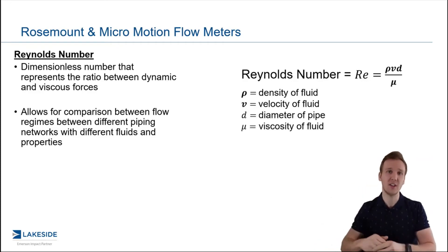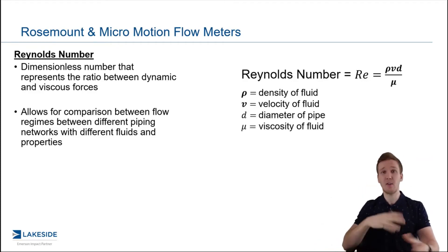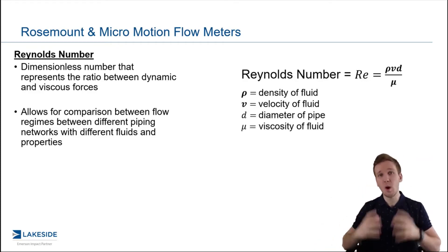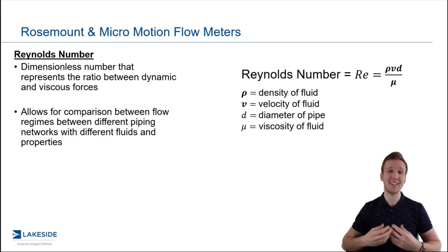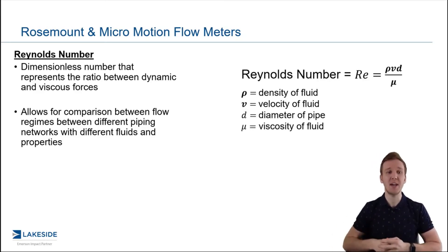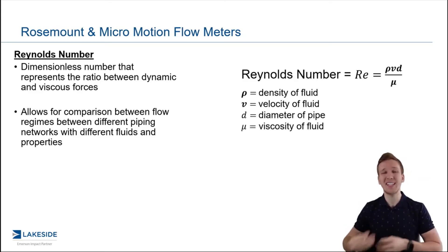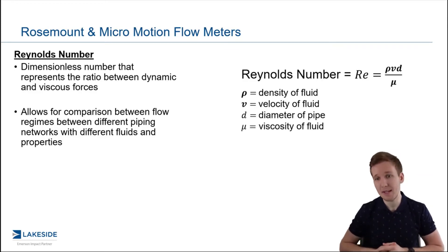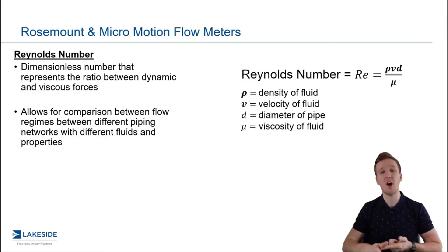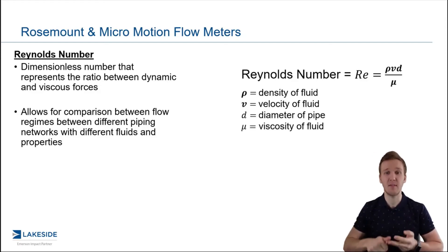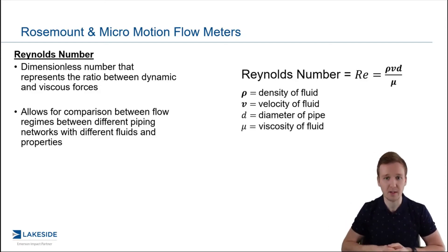Here's what the equation looks like. But for all intents and purposes, what we care about for the Reynolds number is it allows us to compare different flow regimes between different piping networks, and this allows us to get a better understanding of what the flow conditions are within that piping network. As you can see, it takes into account the density, the velocity, the diameter of the pipe, and the viscosity of the fluid — and that is ultimately the Reynolds number.